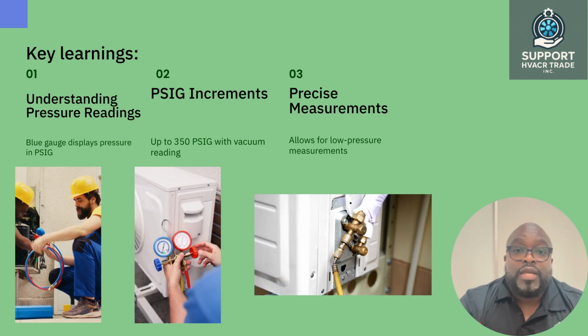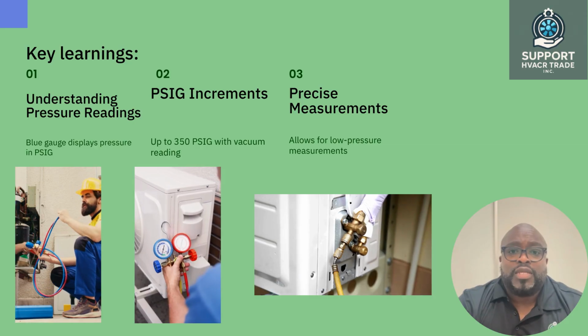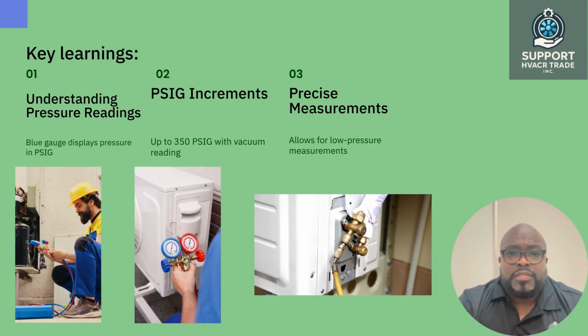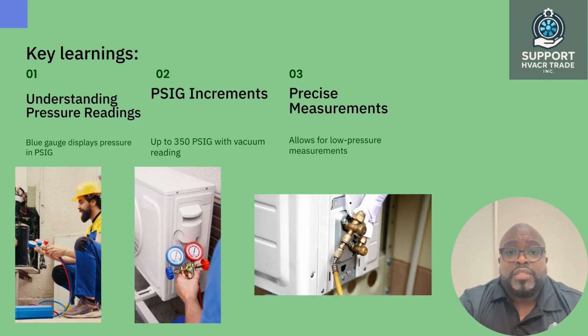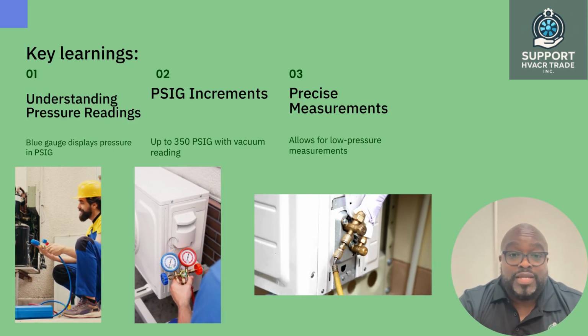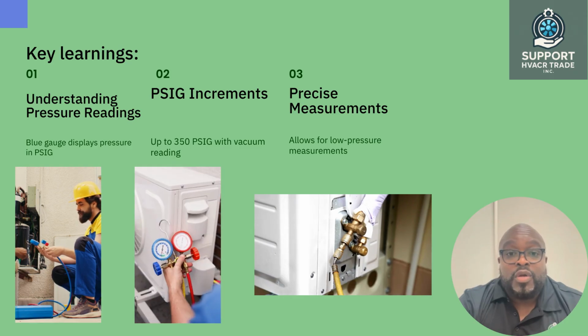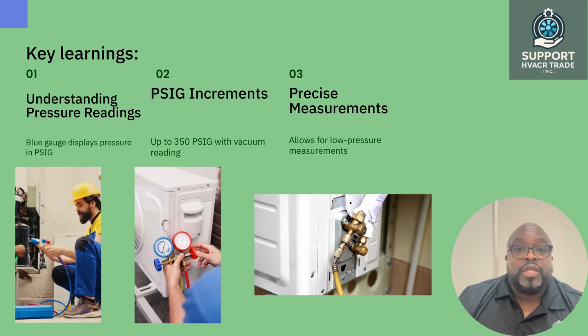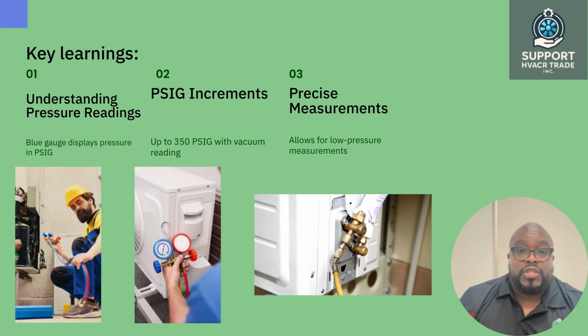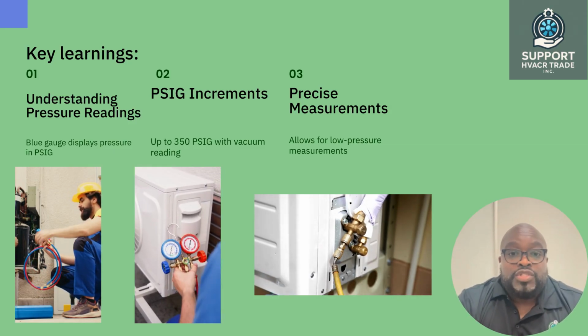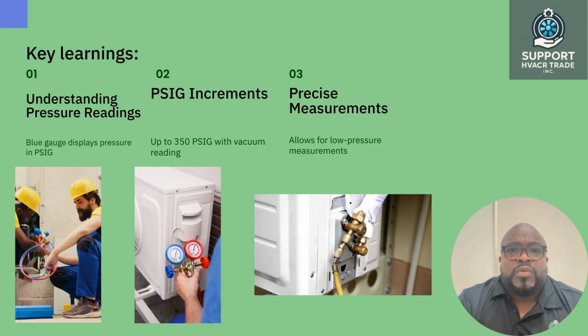Steps for connecting the manifold gauges. Follow these steps to connect the manifold gauges correctly. Prepare the system. Ensure that the HVAC system is turned off before making any connections. Connect the hoses. Attach the red hose to the high-pressure port and the blue hose to the low-pressure port of the manifold gauge. Ensure that the fittings are secure.